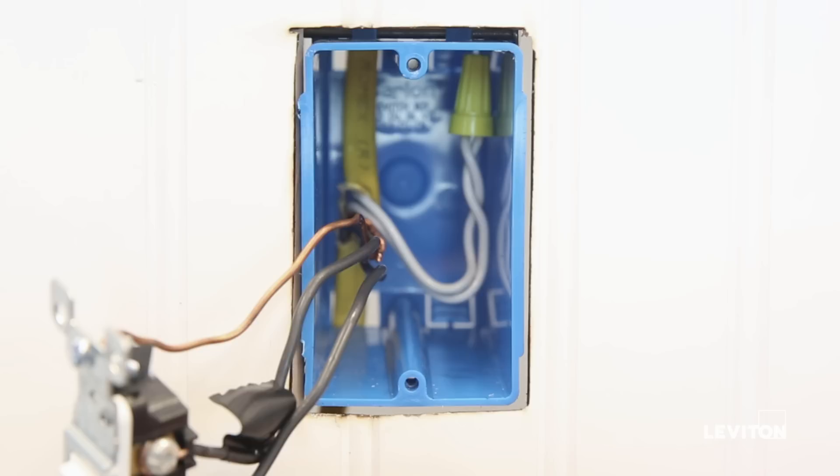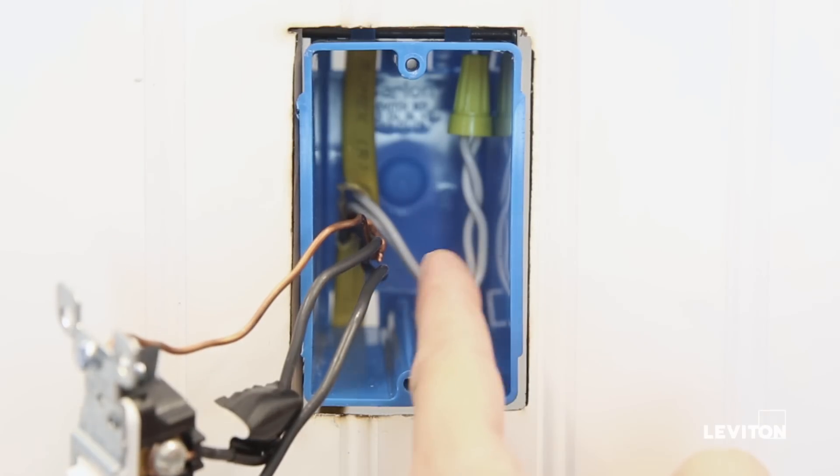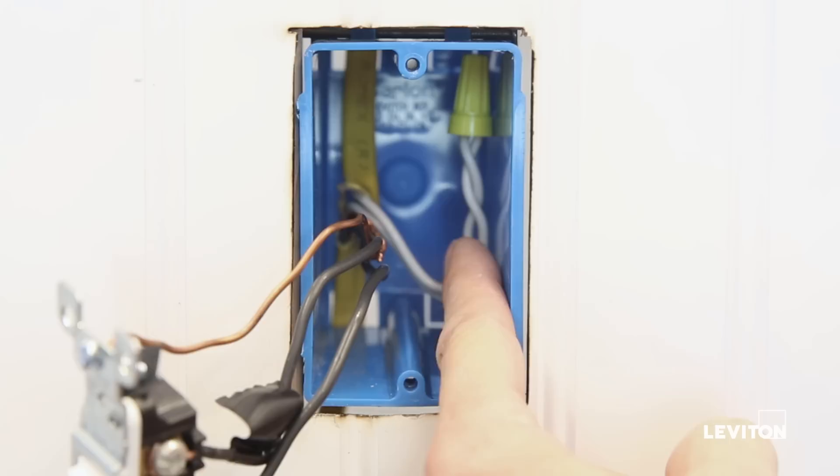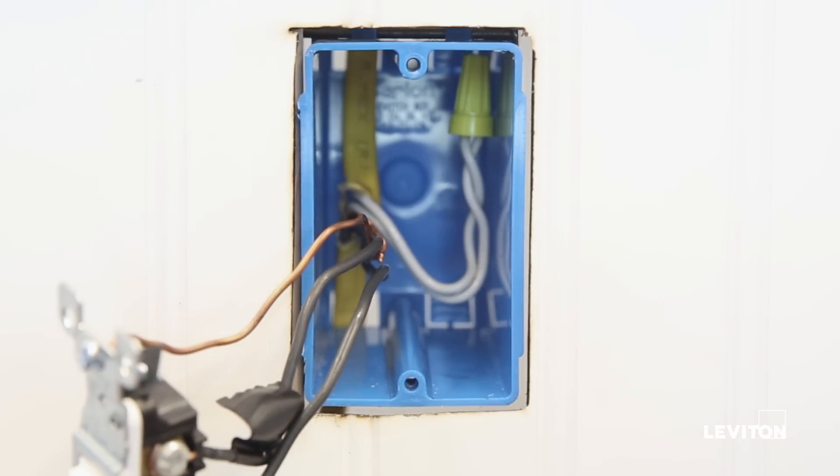If the two controlled leads are black, look in the box. You should find two whites twisted together, capped with a wire fastener. You have a neutral.